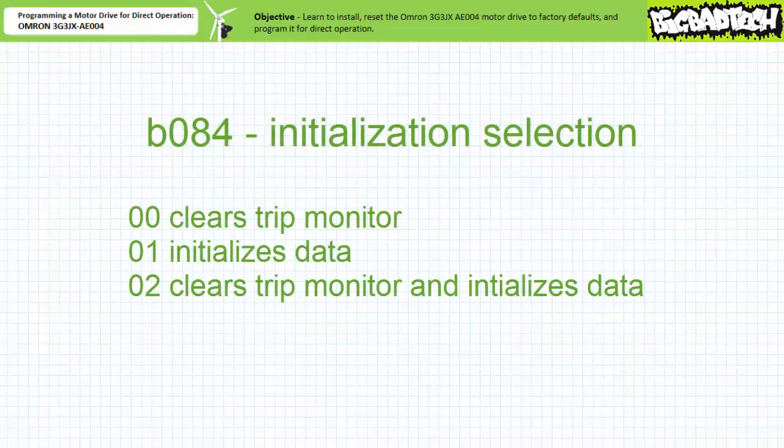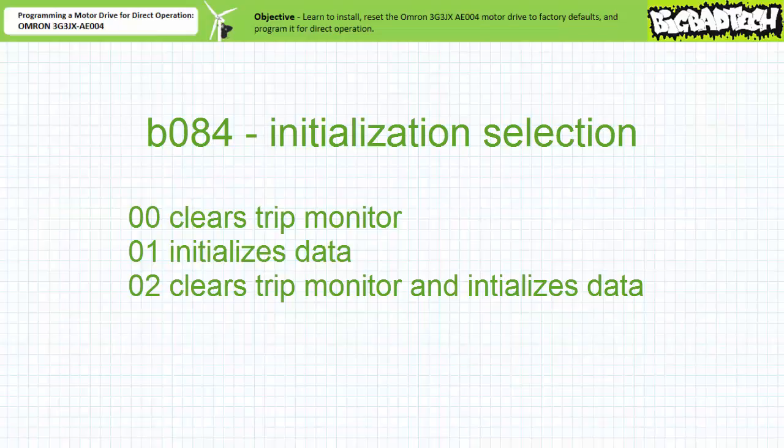Let's use the quick parameter selection method to navigate to the initialization protection parameter B084. Those following along in the user's manual note that this entry correlates to probably the most important parameter in the whole user's manual, notably the ability to clear any previous errors and reset this drive to factory default conditions.